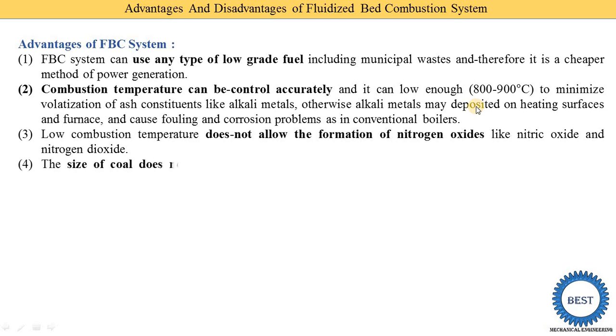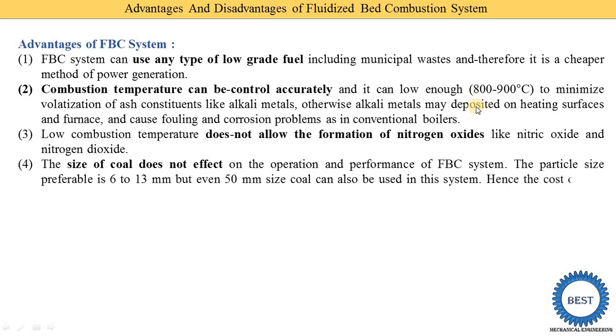The fourth advantage is that the size of coal does not significantly affect the operation and performance of the FBC system. The preferable particle size is 6 to 13 mm, but even 50 mm size coal can also be used. Hence the cost of coal crushing is reduced, unlike in pulverized fuel systems where coal must be crushed to a very small size before use.